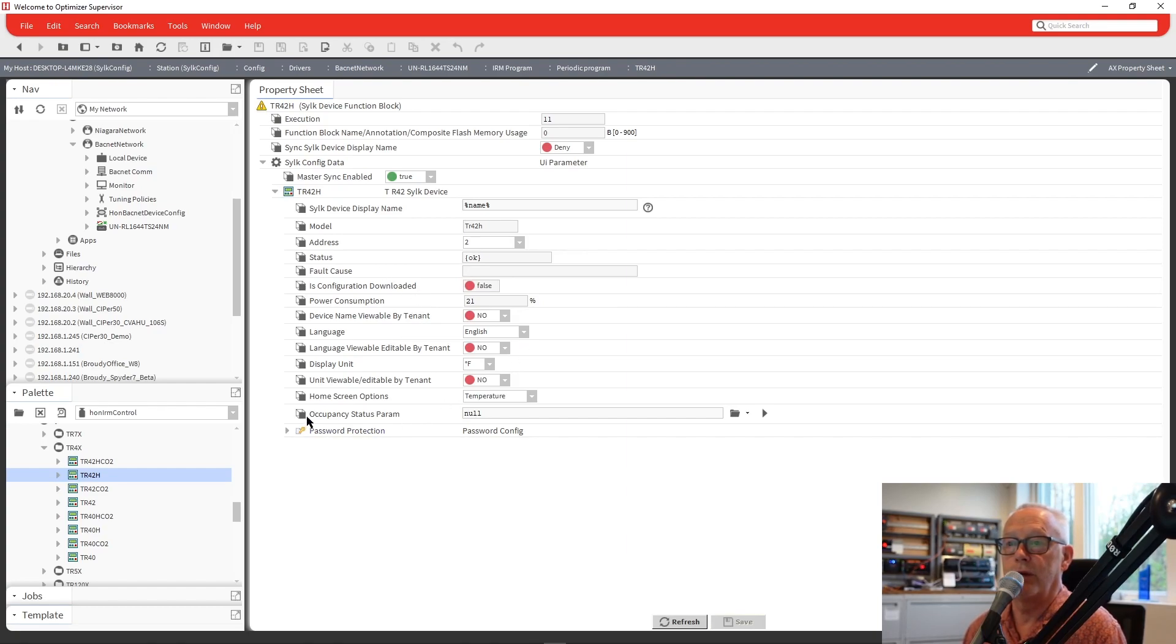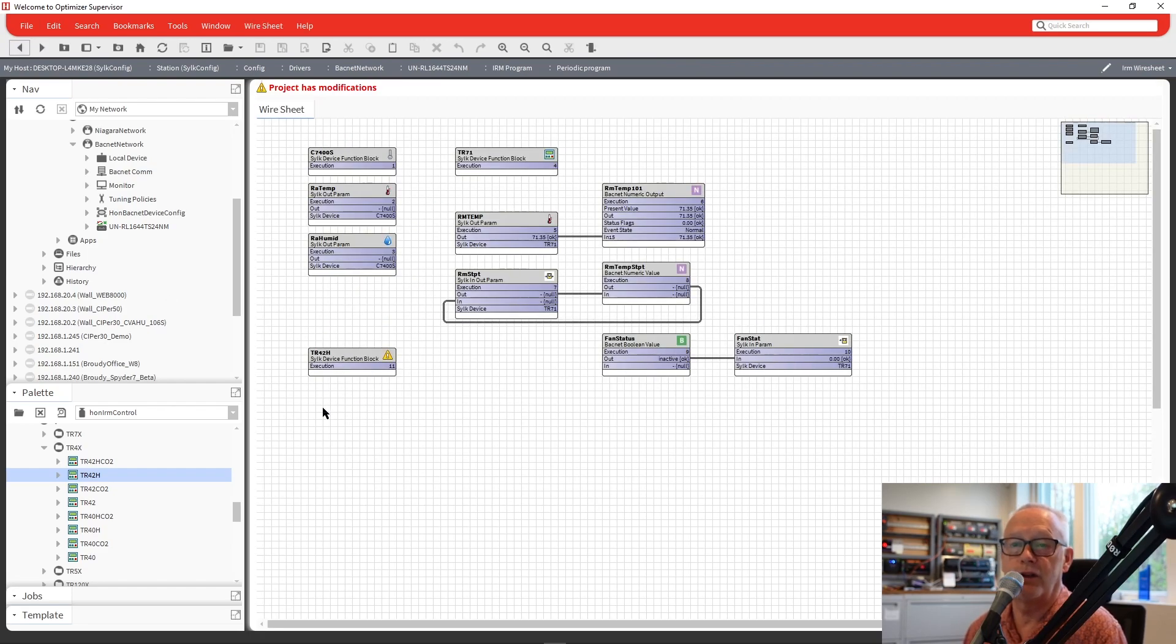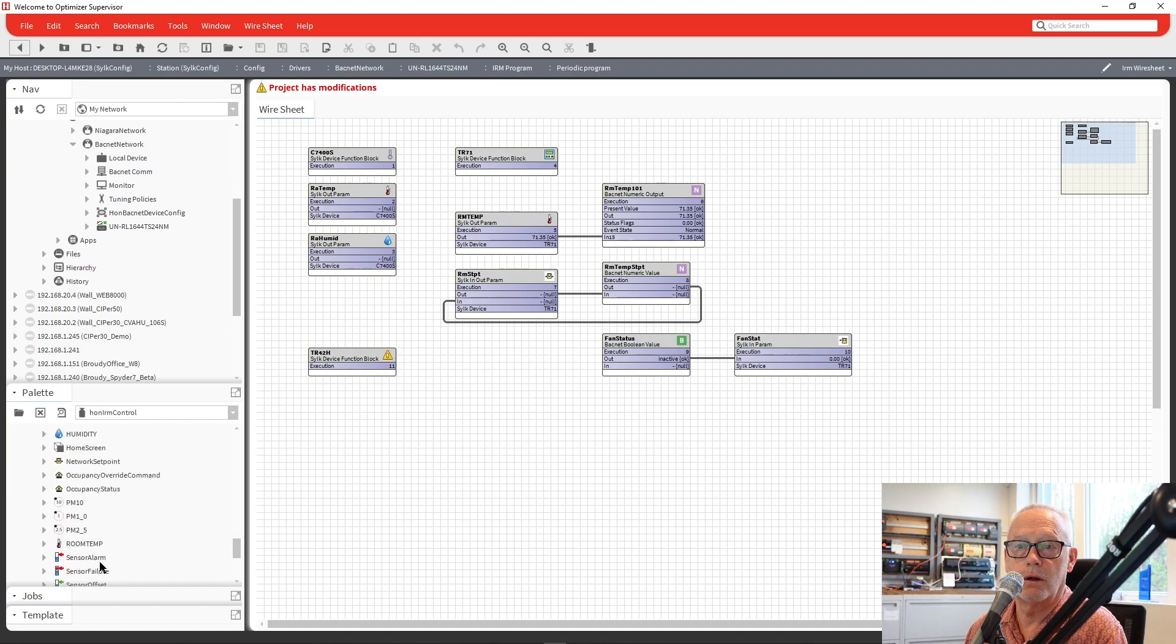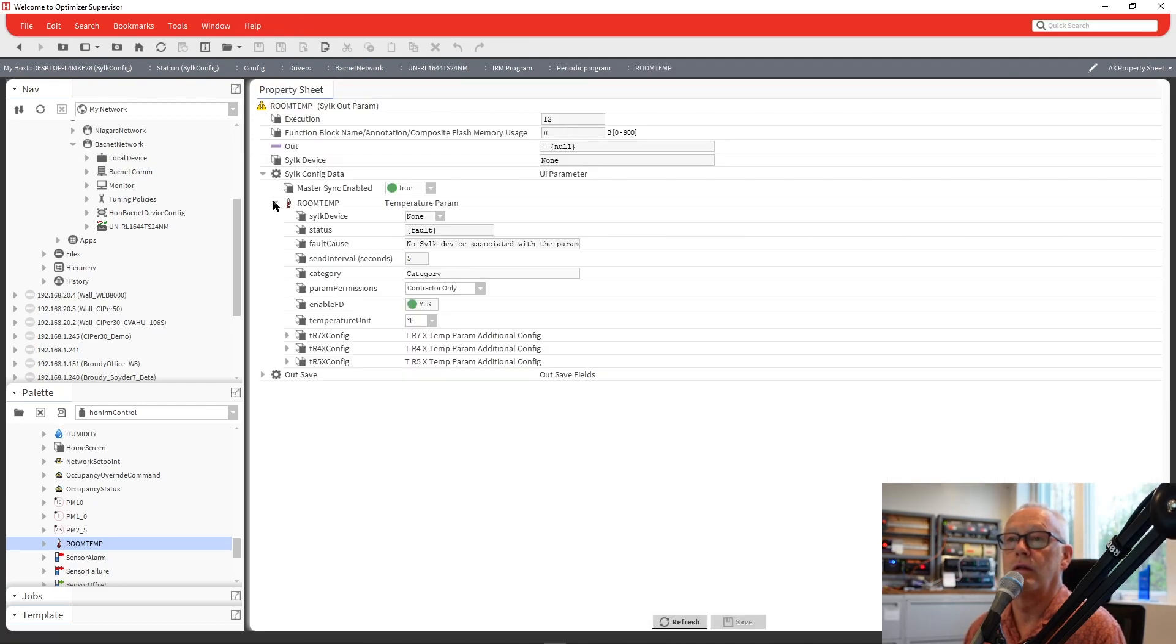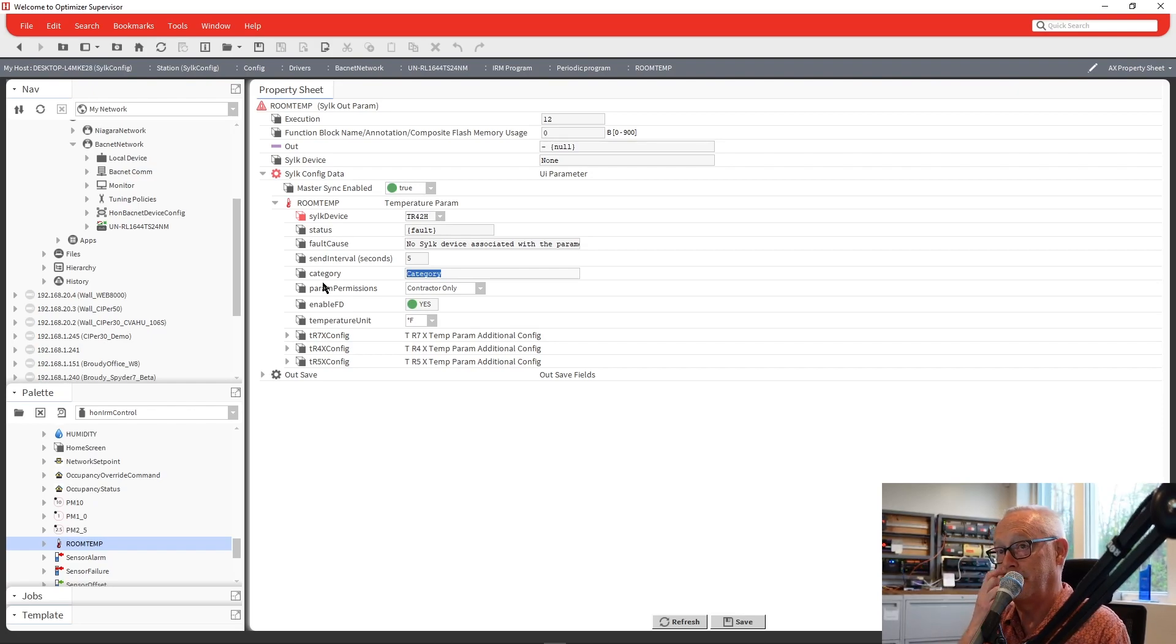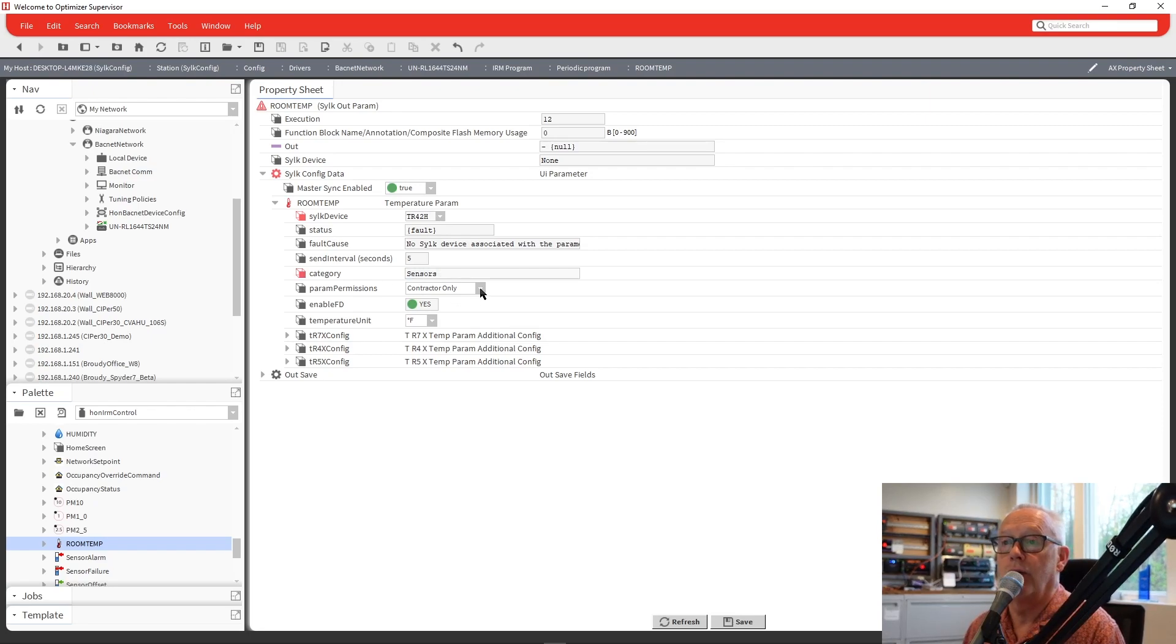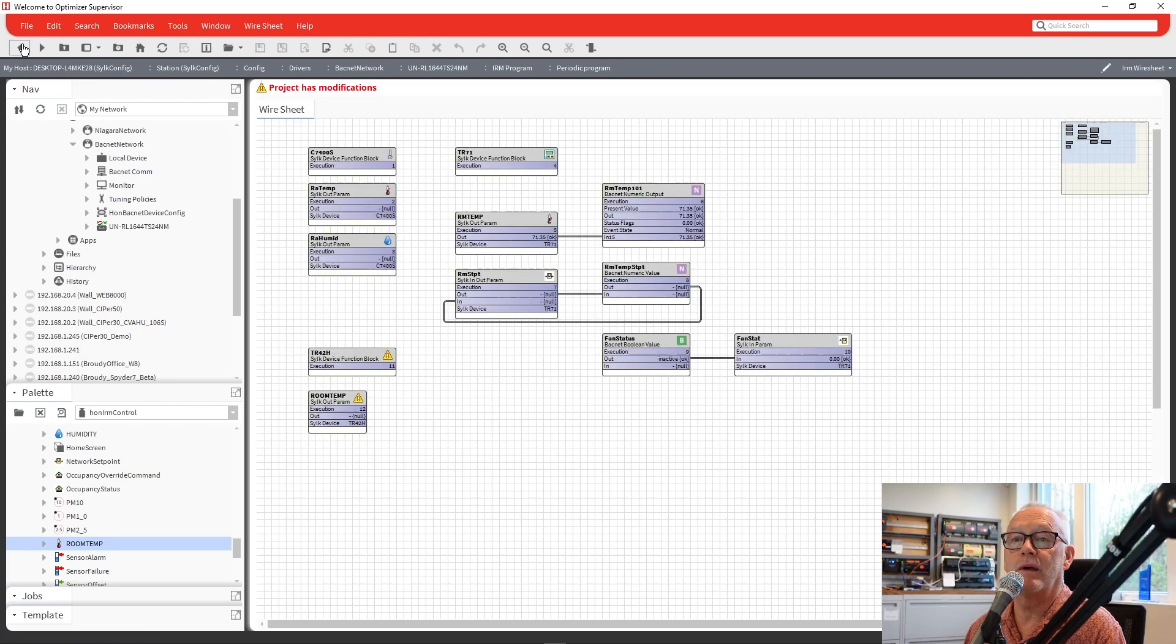And address 2 is fine. We can go through here, occupancy status parameter. So it's going to require us to put it in a parameter for this. Otherwise, it'll fail out when we go to validate. So if we go down to our parameters, first thing we'll do is we'll bring in our space temperature. Drop that down here. Go in. Tell it we want the TR42. And actually, we still do have the categories because it could always be moved to a different type of device. So categories always exist. I'm just going to still say sensors there. We want the tenant to read it. Temperature units in degrees. And that should be all we need to do there. Hit save. Come back out.